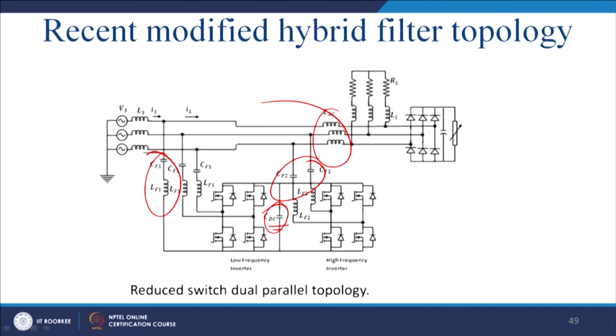Then what happens if there is unbalance? There will be a problem of DC voltage fluctuation. Instead of that, we connect it to the negative half of the DC bus, and thus the fluctuations get eliminated. This topology works very well, and we have shown some results in our shunt active power filter. There is a topological improvement, and it is a reduced cost solution compared to Akagi's version.